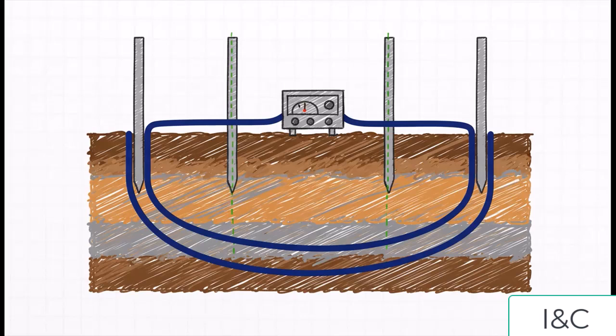Here's what the little magic box does: the meter pushes a known amount of electrical current into the ground through the two outer rods. At the exact same time, it's measuring the voltage difference that pops up between the two inner rods. From that current and voltage, it can calculate the resistance.